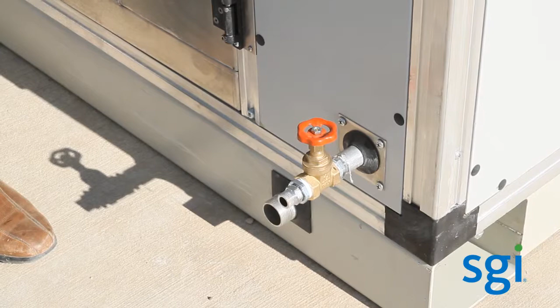So we're back on the outside, and I just want to mention real quick the water entry, which is a story in itself. What you see here down below, the red item there, is actually the entry of the water that cools the entire modular data center. It's a standard garden hose size connection, a 3/4 inch connection, that cools this entire server load. This particular unit runs about 700 kilowatts of IT compute power, all cooled by this simple connection here.